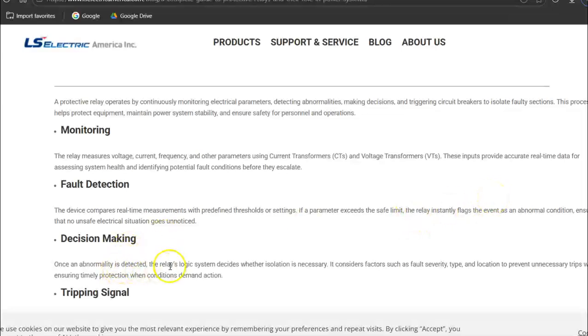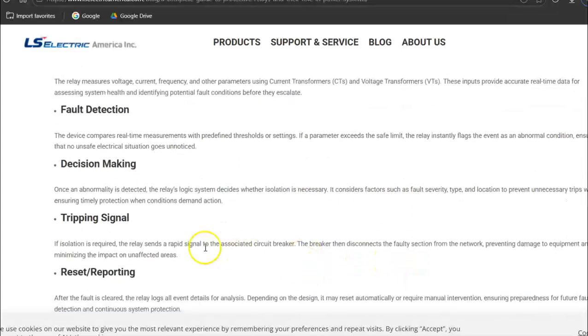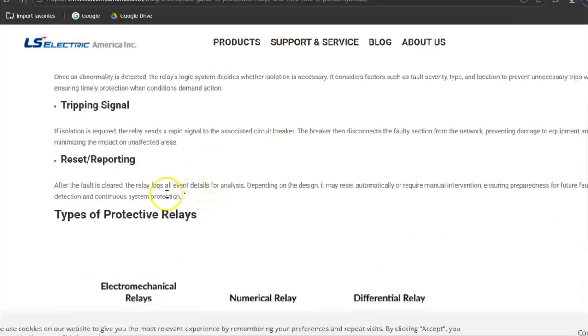Once the condition is detected, the relay's logic system decides whether isolation is necessary. It factors in fault severity, type, location, because you don't want an unnecessary trip shutting down a huge area. It will then generate a tripping signal. So there's usually a circuit breaker involved. This relay will then send the signal to the circuit breaker, which trips and opens the network. After the fault's cleared, the relay logs all the event details for analysis, and it may automatically reset, or can be set to automatically reset or have to be manually reset.